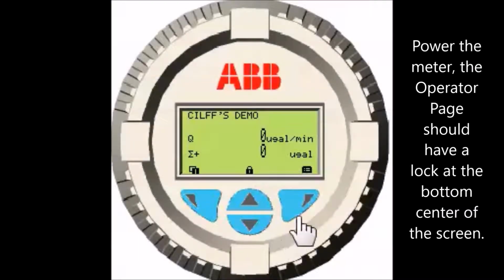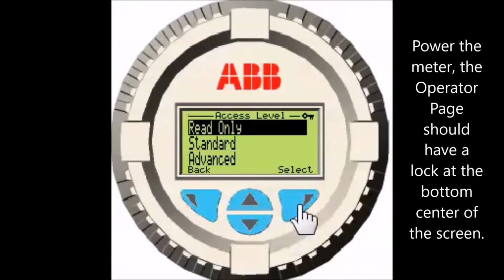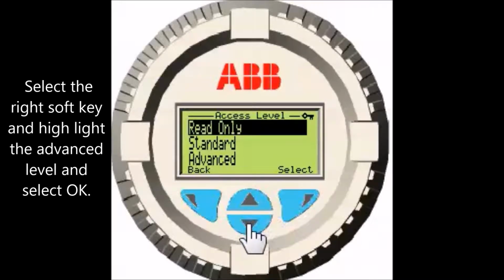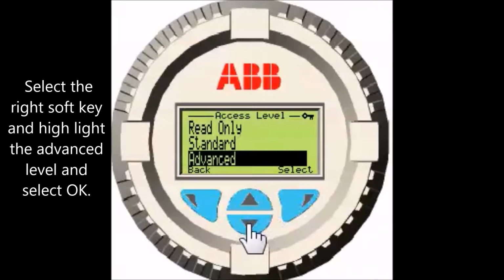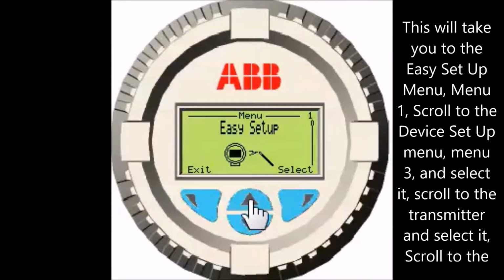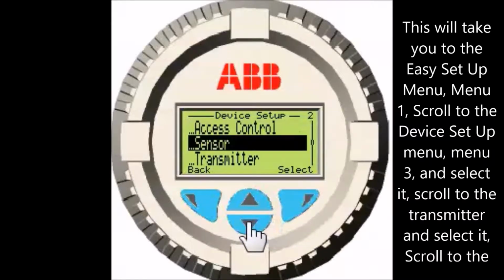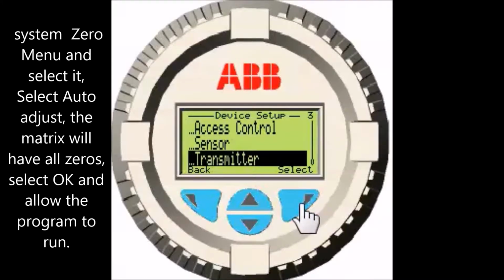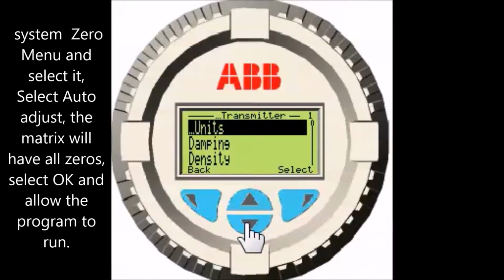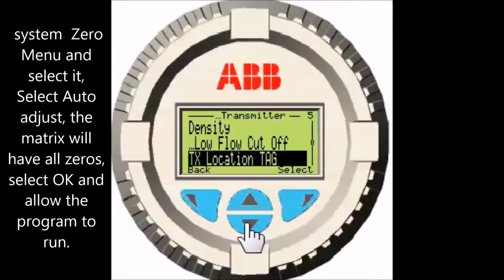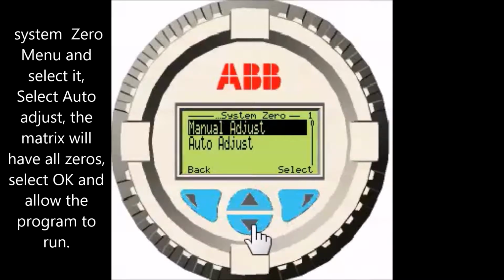Power the meter. The operator page should have a lock at the bottom center of the screen. Select the right soft key and highlight the advanced level and select OK. This will take you to the Easy Setup menu, Menu 1, scroll to the Device Setup menu, Menu 3, and select it, scroll to the Transmitter and select it, scroll to the System Zero menu and select it, select Auto Adjust. The matrix will have all zeros, select OK and allow the program to run.